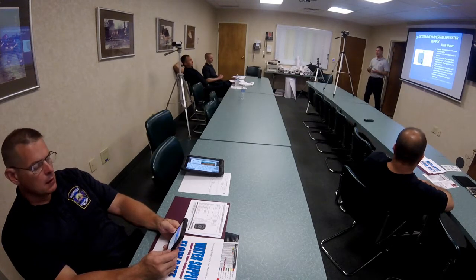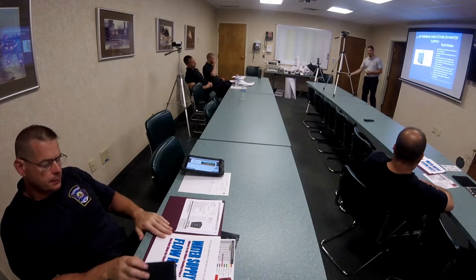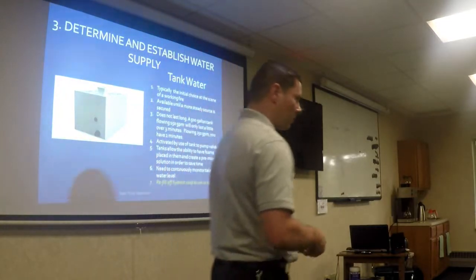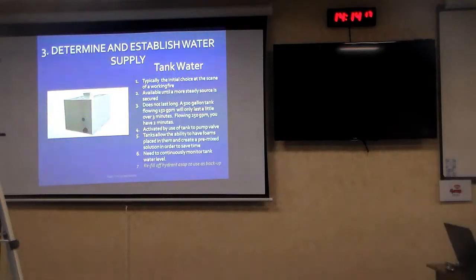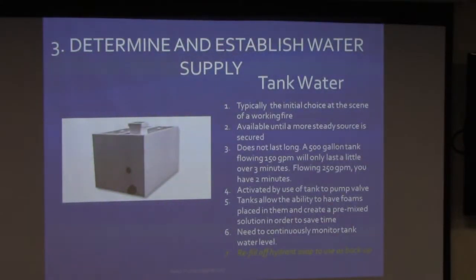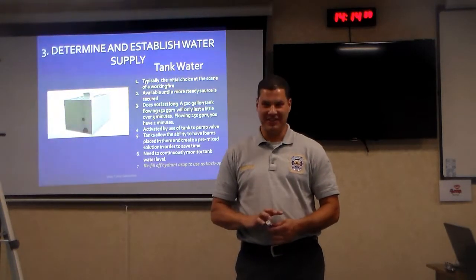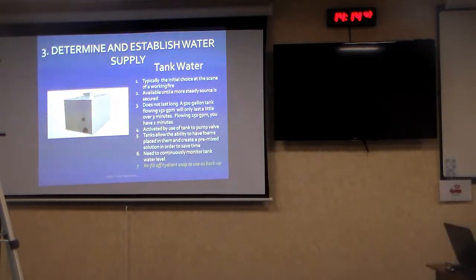Maybe we're in that range, so 150 times 2 is 300, that's a 2-minute frame, and maybe a little after that. So about 2 to 3 minutes is how long the tank would last if you're flowing a steady 150 gallons per minute. Why is that 2 to 3 minute time frame important? Because you've got to get a water supply established. Exactly, so that's key for you when you're doing your scenarios: you have 2 to 3 minutes after the line is charged to get off the truck, go make your connection, and do all that stuff. So what happens if you don't make it in 2 to 3 minutes? You get an interruption in your water supply, and that's going to be bad, so keep that time frame in mind.